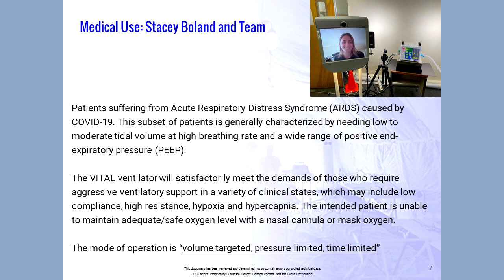You see here at the bottom a very important statement. The mode of operation for this ventilator is what we call volume targeted, pressure limited, and time limited. This is quite an important statement, and you will see it on multiple occasions. When we worked with the FDA and with hospitals, it was very important to communicate, because doctors and trained operators of the ventilator really need to understand its mode of operation. We ran into this question and topic repeatedly.